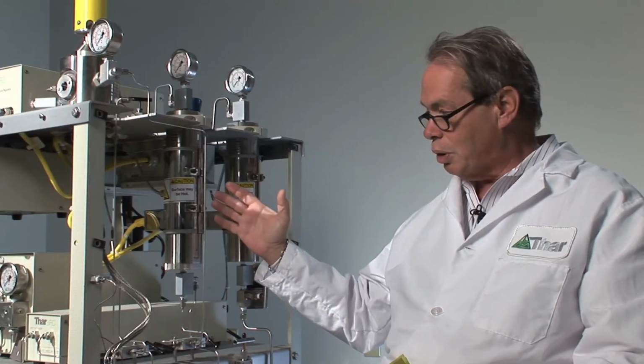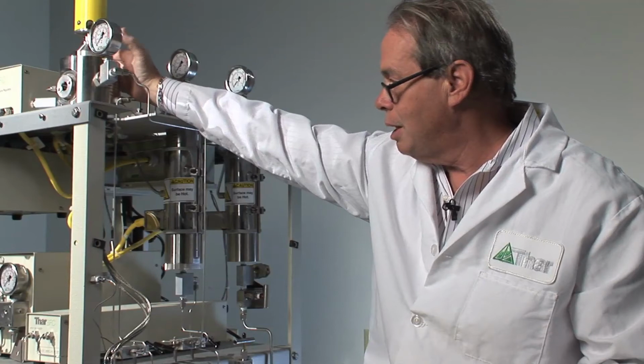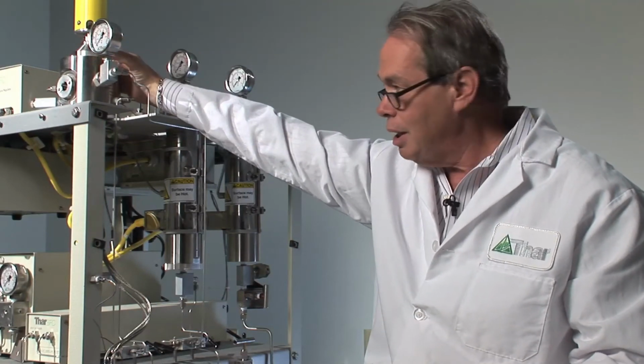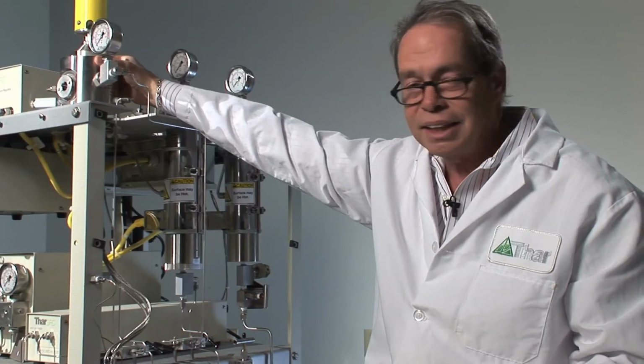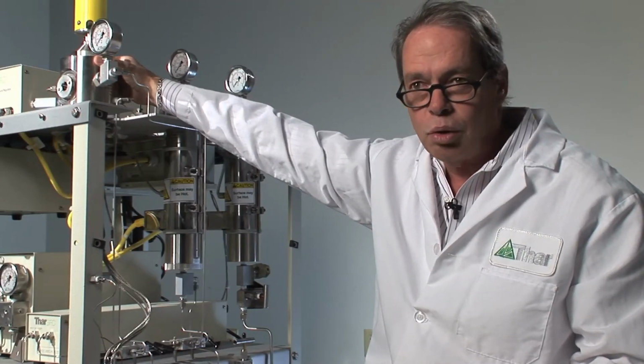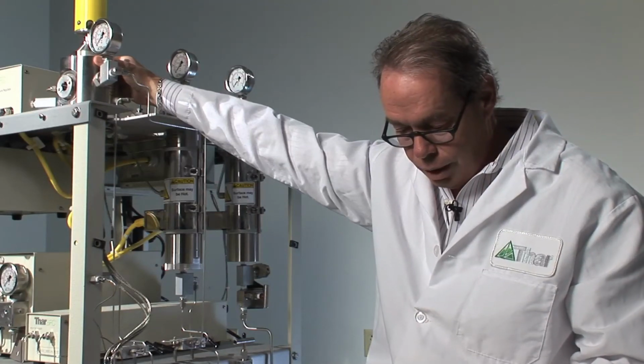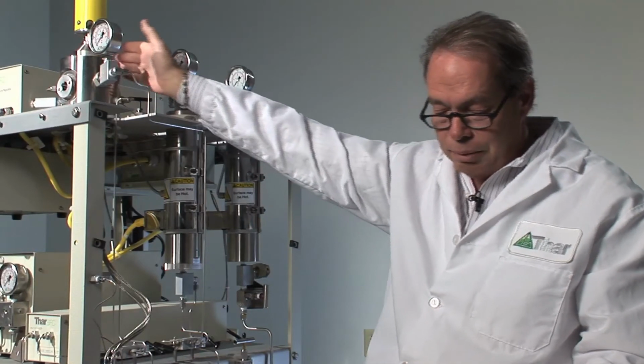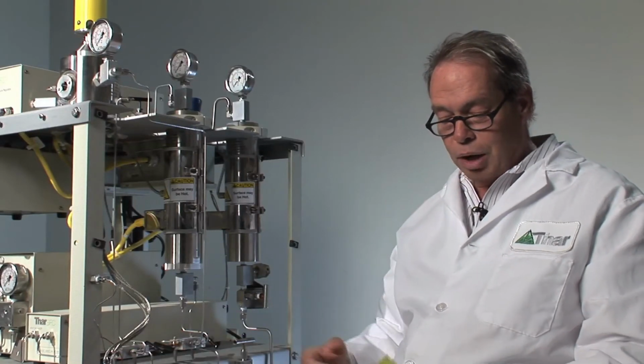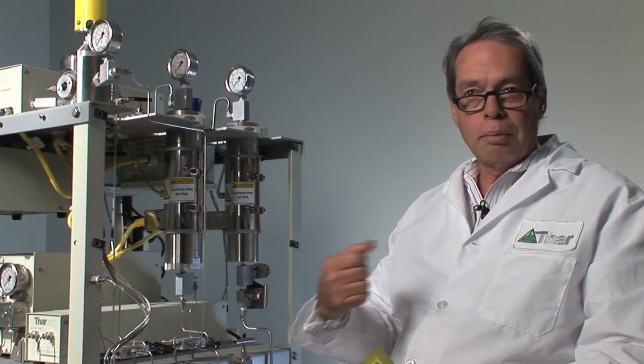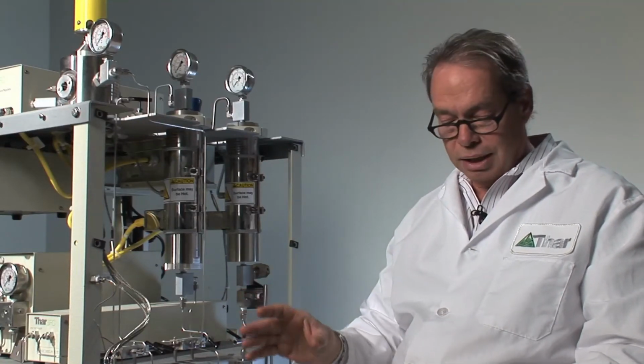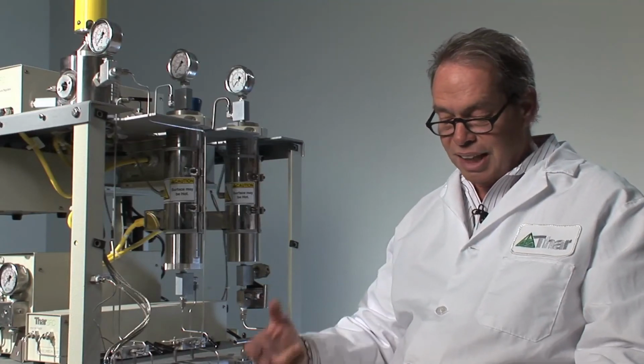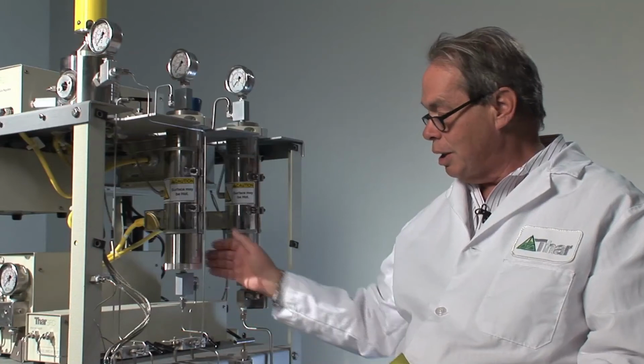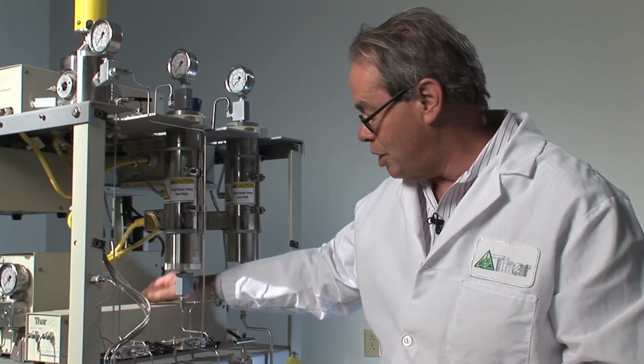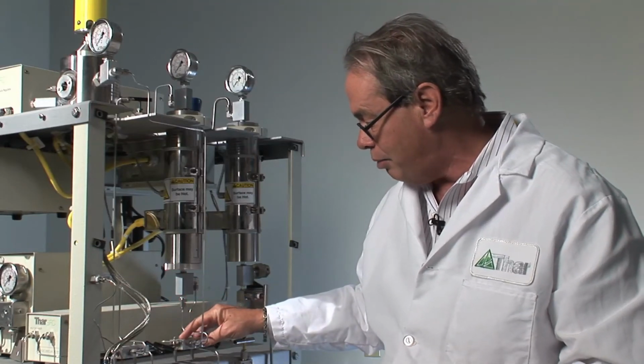Dissolving the same materials in a supercritical fluid, and in this system, the material that we want to make into a powder is in this chamber at high pressure, and it's in the presence of an organic solvent. It's dissolved in an organic solvent. Dissolving the same materials in a supercritical fluid and rapidly spraying through a nozzle as it is depressurized eliminates the problems of forming pastes and very broad particle size distributions. The system uses the same fluid delivery components as the extraction system. So the chiller, the pumps, the heat exchangers are all the same up to the point of this three-way valve.